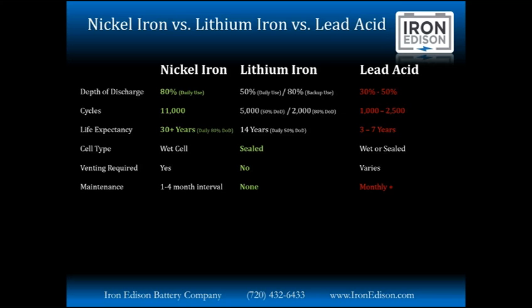And above and beyond that, we recommend replacing the electrolyte in a nickel iron battery about once every 10 years or so. That's going to help prolong the life of it. Over time, you're going to have a very slight loss in electrical capacity, and that's due to a carbonate buildup in the electrolyte. By replacing the electrolyte every 10 years or so, you'll recover that capacity loss. And by doing that every 10 years or so, really the battery should last indefinitely.